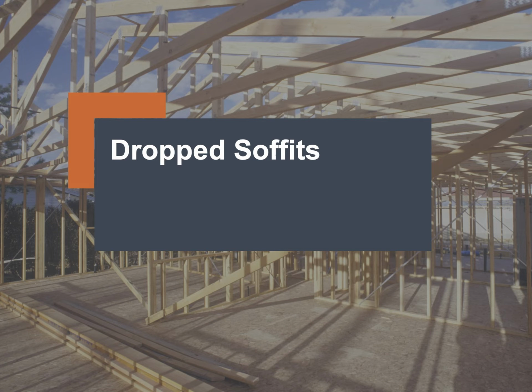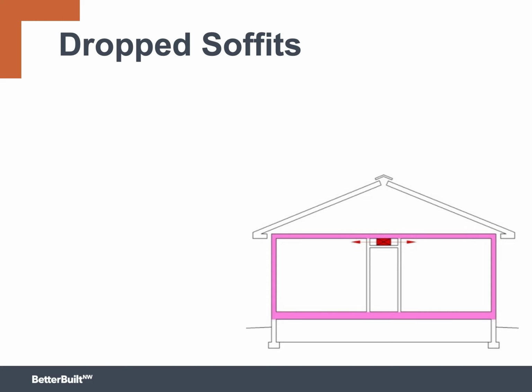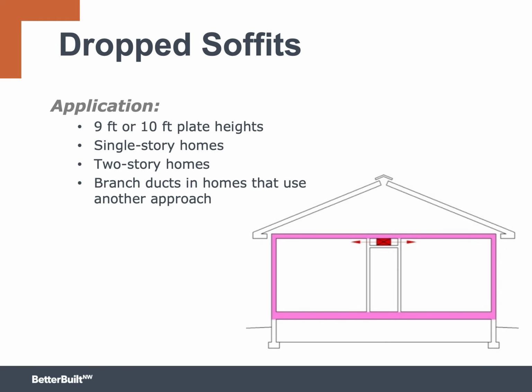These are commonly used in residential construction to contain plumbing, place a cap on upper cabinets, or enclose light fixtures. And oh, by the way, you can use drop soffits for ducts too. It can be the most economical approach, and so it's often used by affordable housing developers. Soffits are framed below the thermal boundary, that is the true ceiling, to create a space to run the ducts. This approach is one of the few that brings ducts into what has traditionally been the conditioned space. It works well with ceiling heights that are about 9 or 10 feet.